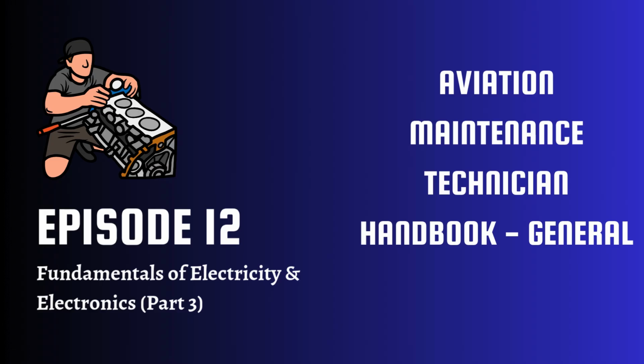D. Motor control and maintenance. Reversing rotation. Critical task sometimes. What's the absolute rule for reversing a DC motor? You must reverse the direction of current flow in either the armature or the field winding, but not both.